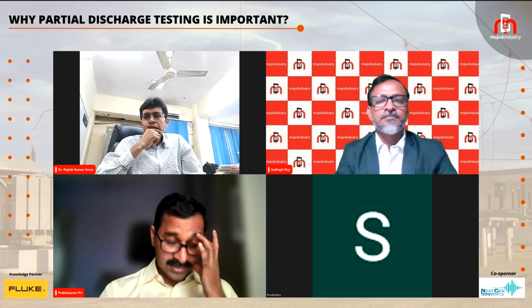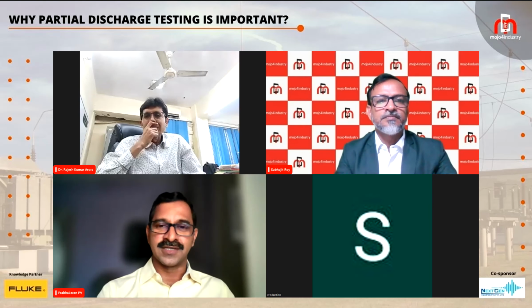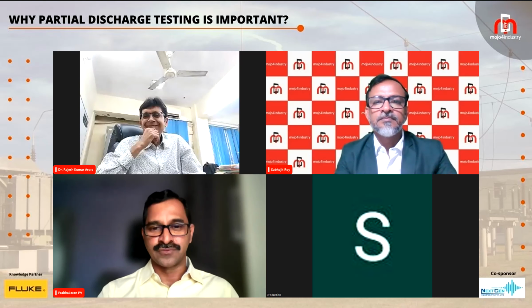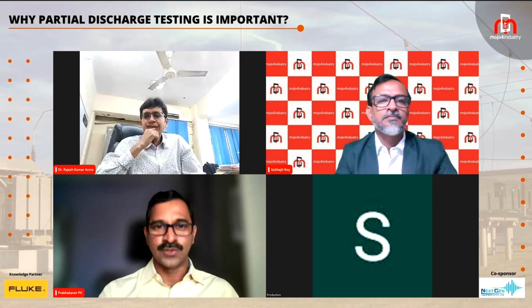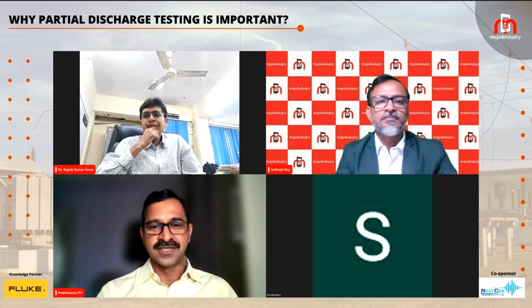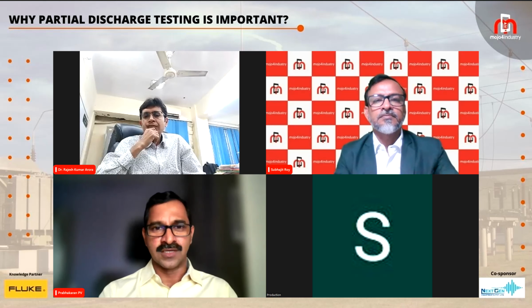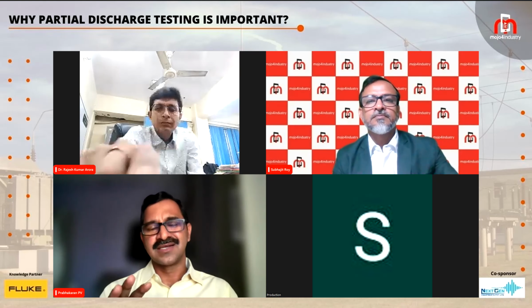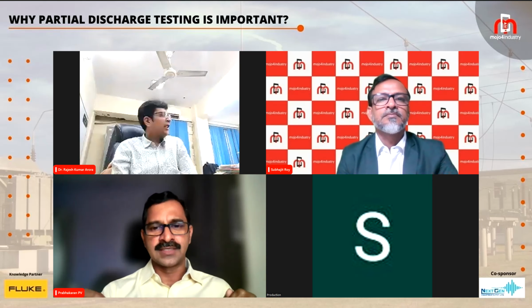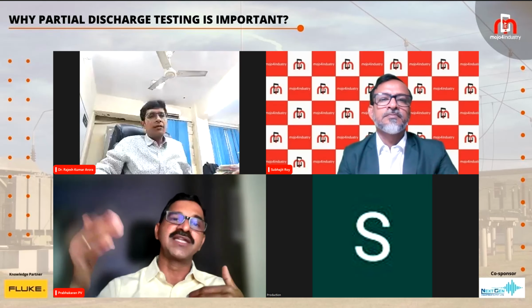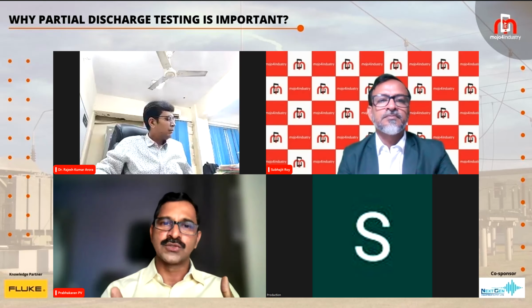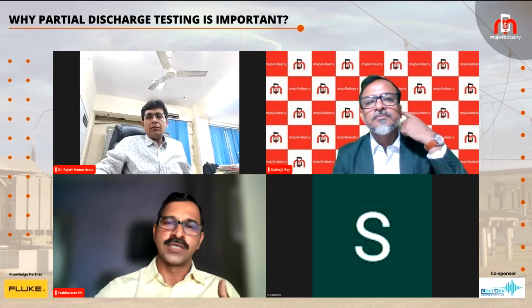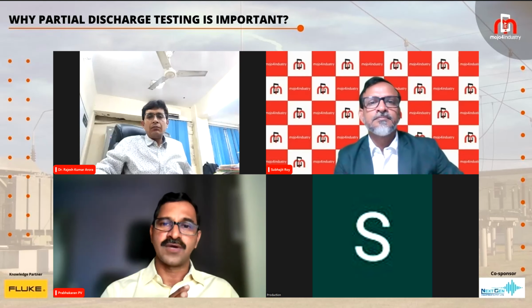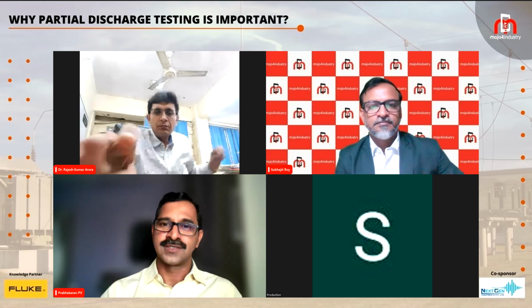Tan delta is one method of testing, but it won't give you the entire picture of partial discharge. It has some limitations of its own, and it's fairly bulky equipment, so taking it to various locations isn't easy. Every instrument has its own pros and cons. An acoustic imager, on the other hand, is much easier to use, it's portable, and you can detect partial discharge from a distance. Safety is paramount since you can't go too close to the equipment, so you go a bit further and do the acoustic imaging or analysis from a farther distance, which makes it easier and more accurate.